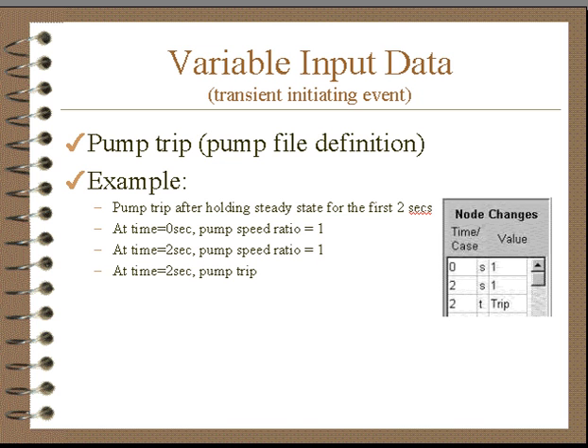If you have a pump file, you can actually designate either speed or a trip. A trip allows us to calculate the rundown. This illustrates a pump trip where at time zero to two the steady state conditions are held, and then at time two the pump trips. The selection we make here is the pump trip.